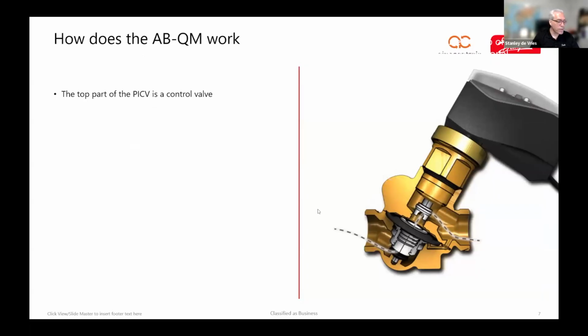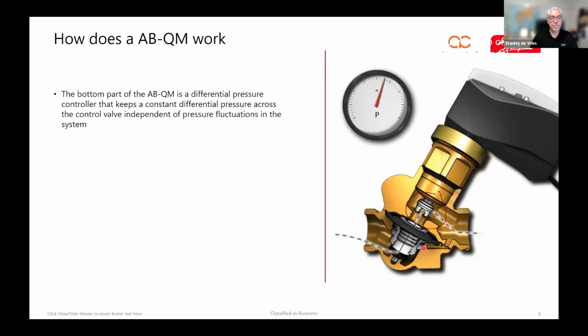We have the top part that is here. That is just a control valve that functions like a normal control valve. It will just open and close based on an actuator that's on top, so there is nothing really spectacular. But if you look at the bottom, this is where the magic happens, because that is a pressure controller. The pressure controller responds to the pressure and actually maintains a constant differential pressure across the control valve.